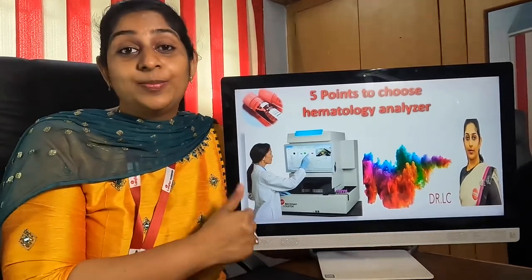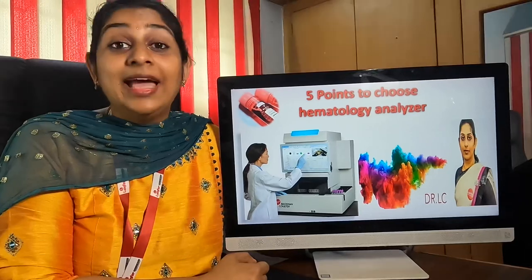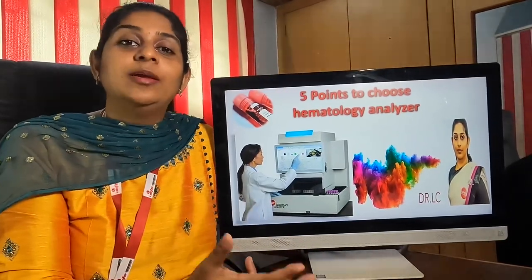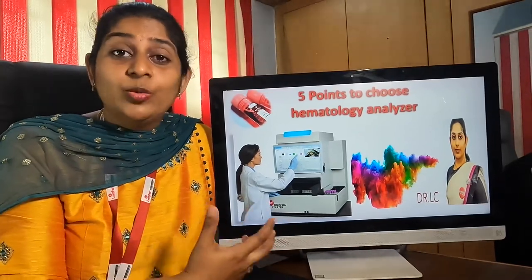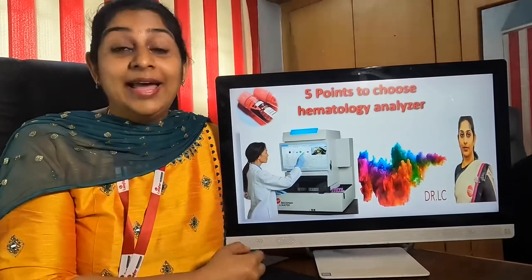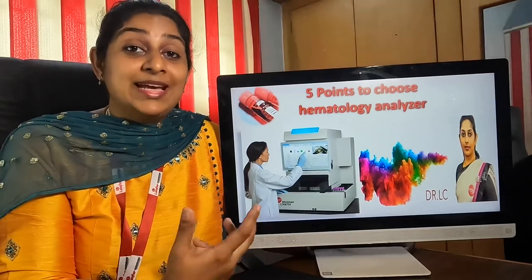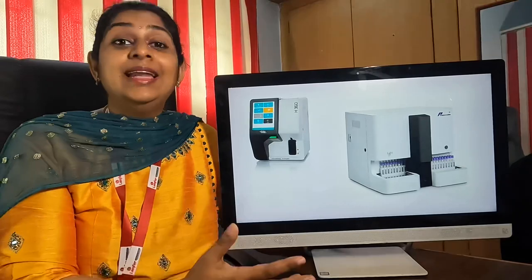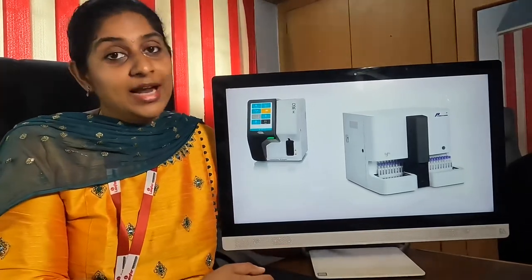The first point is what type of sample you are going to run in the hematology analyzer. You can run blood and also fluids. If you are going to be focused on only blood samples for the CBC count, you can choose a three or five part analyzer. If you are also going to run a good number of ascitic fluid or pleural fluid, then it is ideal to choose a six or seven part hematology analyzer.